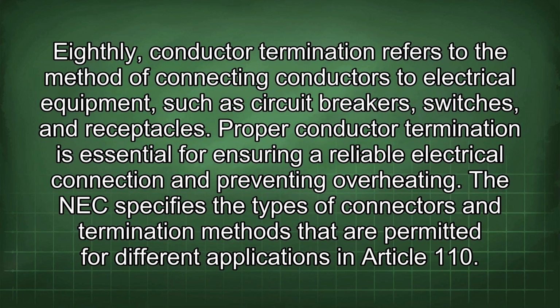Eighthly, conductor termination refers to the method of connecting conductors to electrical equipment such as circuit breakers, switches, and receptacles. Proper conductor termination is essential for ensuring a reliable electrical connection and preventing overheating. The NEC specifies the types of connectors and termination methods that are permitted for different applications in Article 110.